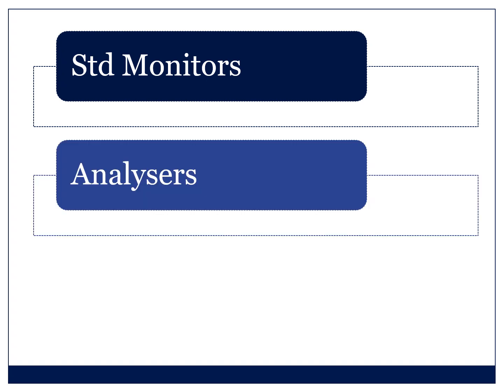You want to check that your analyzers are working. So there's an oxygen analyzer. Part of a machine check is actually to calibrate this. So you calibrate it to room air, which means that the oxygen will read at 21% or 0.21. And then you check that the 100% oxygen using the oxygen flush is giving you that reading. And each machine has got a way to calibrate it.